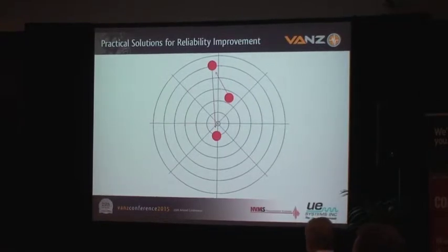But just based on this experience alone, there's a lot of value in recognizing this is good, this is normal, this is how everything typically behaves. We all agree that if it goes up like this, it's bad. I think we should all agree that if it goes down like this, that's also bad. But we seem to be, as a community, so conditioned to focus on keeping the levels below the thresholds that sometimes I think we as a community tend to forget. Our focus really does need to be on change.